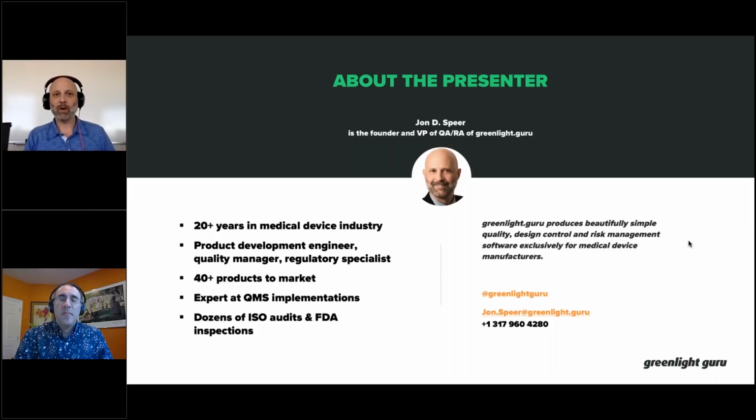It doesn't matter if it's a mechanical product, a hardware product, an IVD, or software. The expectation is that you're defining your design control activities as long as it's determined to be a medical device. And software as a medical device is a medical device, so that means 820.30 applies. That means ISO 13485 section 7.3 applies.